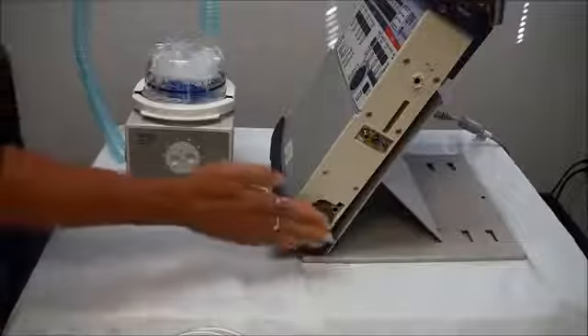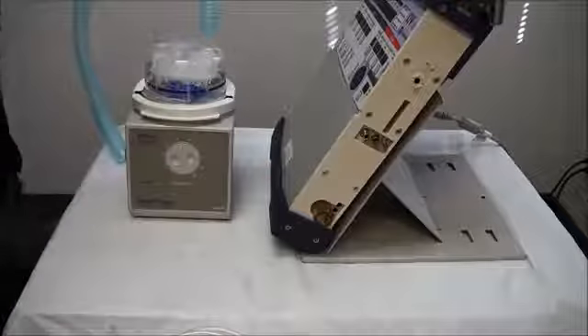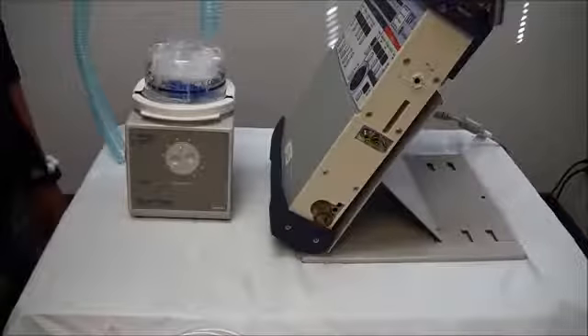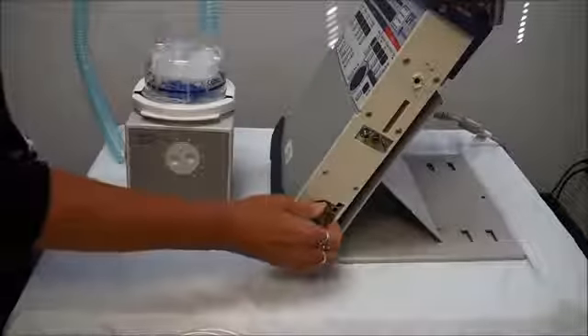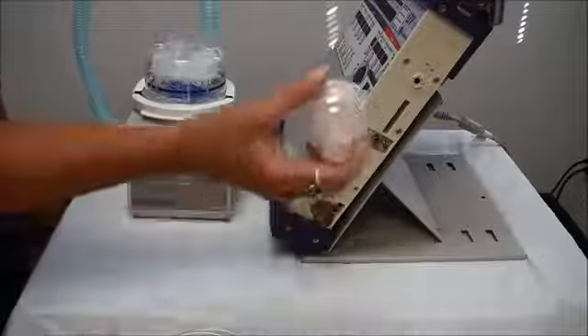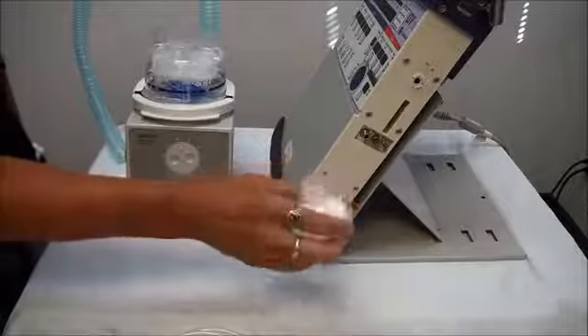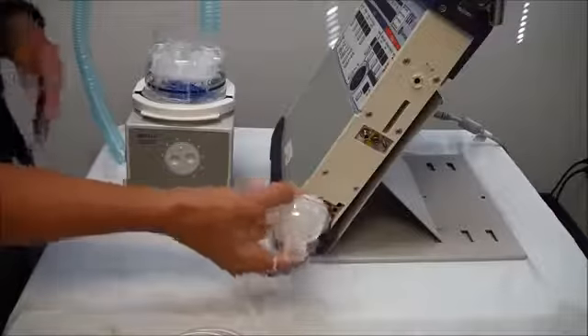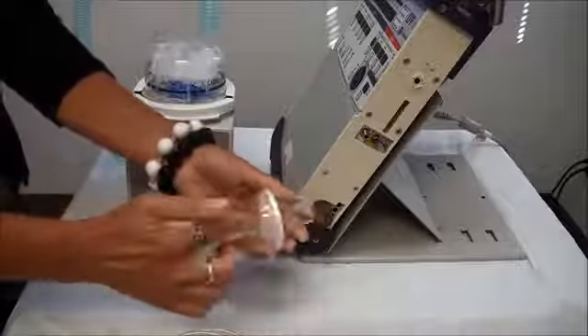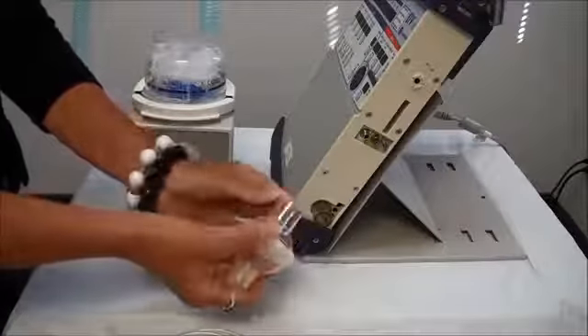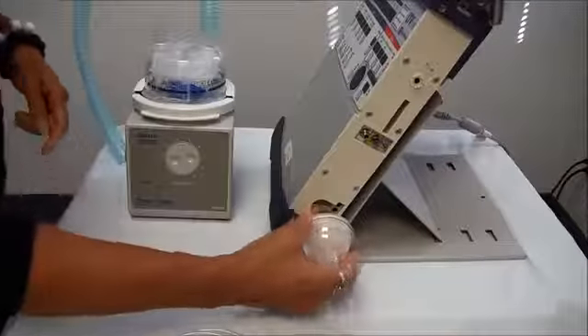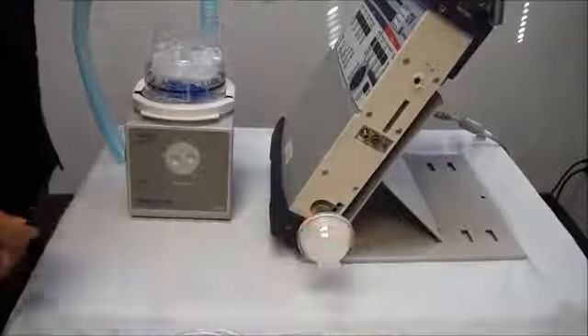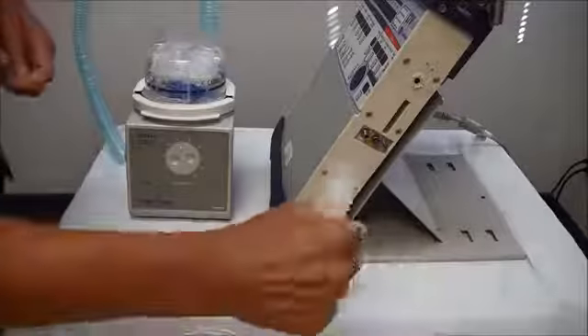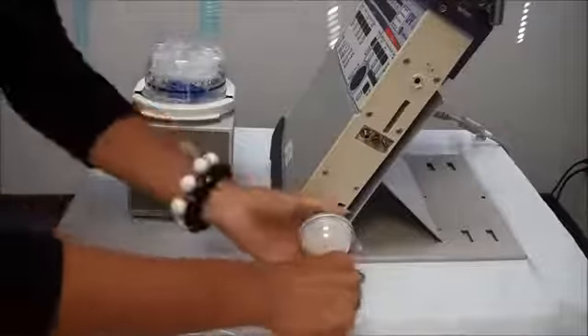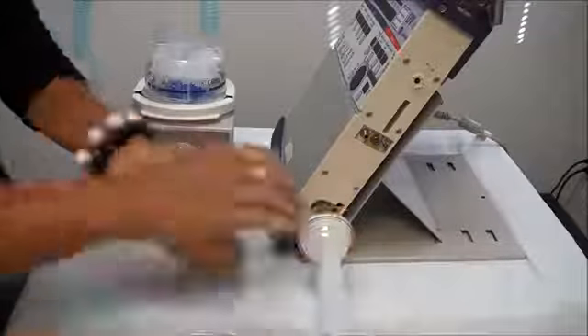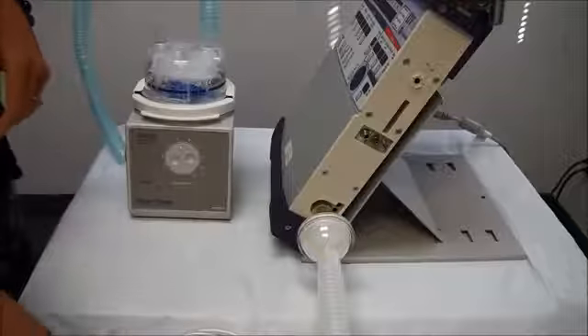I'm going to start down here on the bottom where your large bore tubing is going to connect. You have a connector that's coming out of the ventilator, and you are going to connect a bacteria filter to that. The filter is different diameters on either end, and the larger side is going to connect to your ventilator. So you just want to push that on nice and tight. And then on the other end, your tubing circuit is going to attach. Just like that, your large bore tubing.